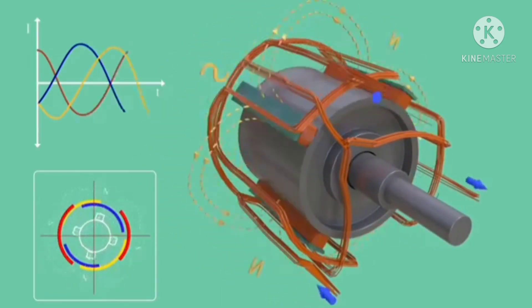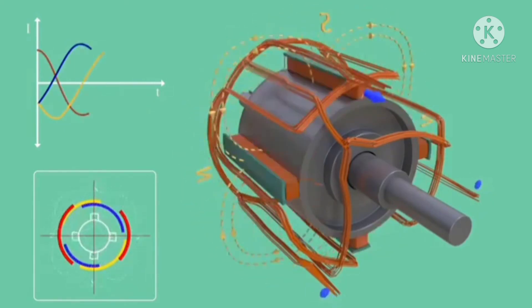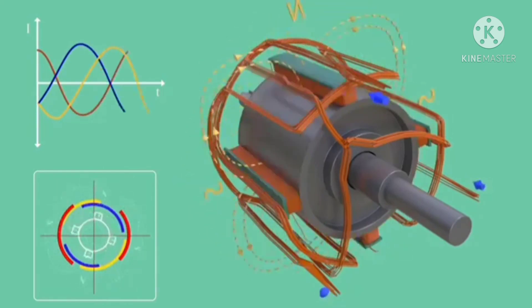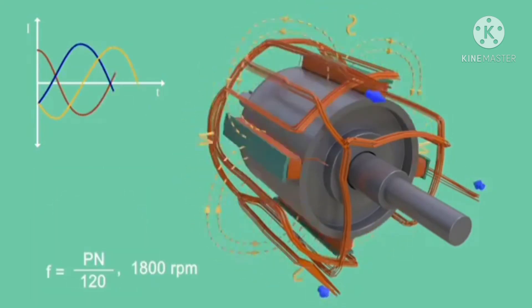It is clear from the equation that in order to produce 60 Hertz electricity, a four-pole rotor should run at a speed of 1800 rpm. Such high rpm will induce a tremendous centrifugal force on poles of the rotor, and it may fail mechanically over time.